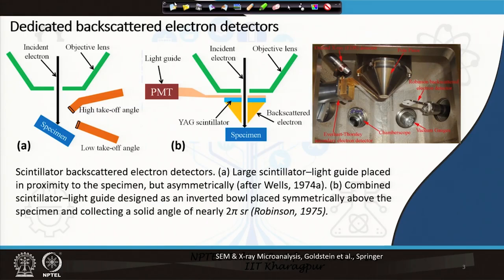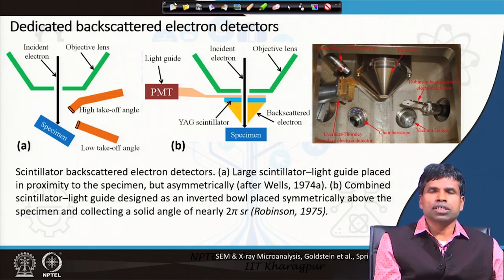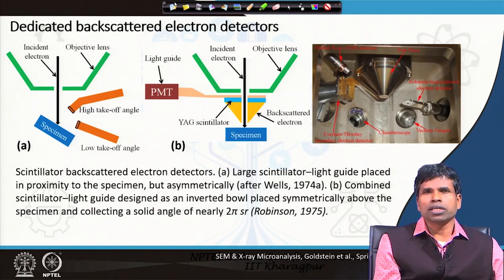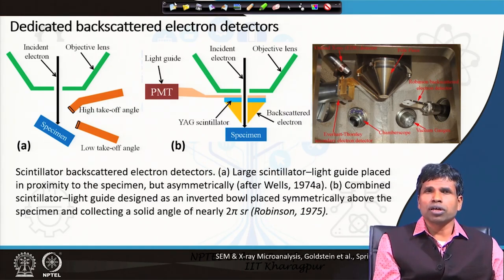In the previous case of the secondary electron ET detector, we used to provide a bias voltage of around 10 to 12 kV to accelerate the secondary electrons and increase their energy when they strike the scintillator material to produce light. But with backscattered electrons, which have higher energy, we do not need to provide a bias to the scintillator — it can remain unbiased and still collect enough backscattered electrons to provide a signal. Secondary electrons have lower energy, so without applying a bias to that detector or scintillator, we would not collect any secondary electrons at all.